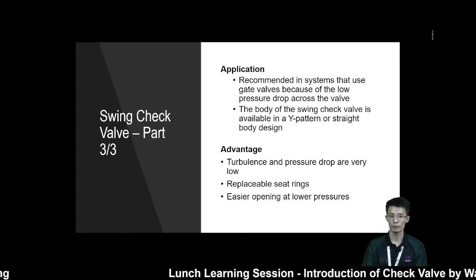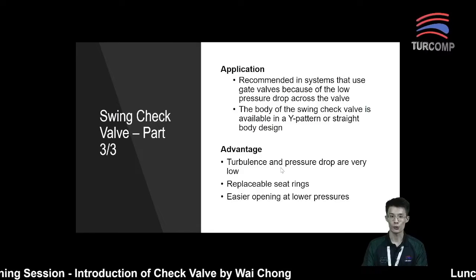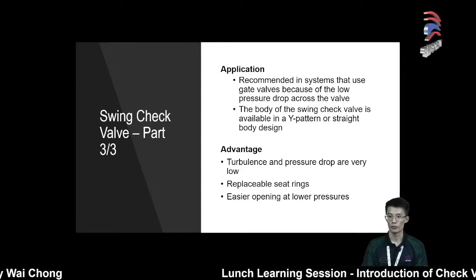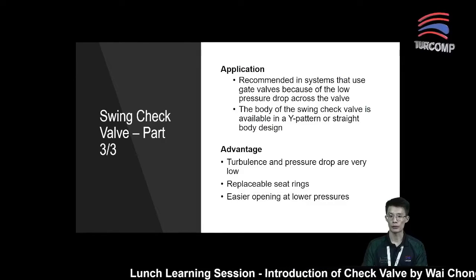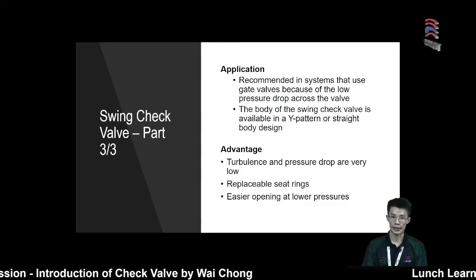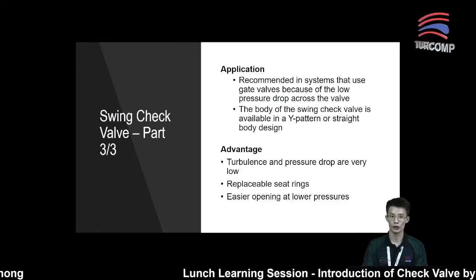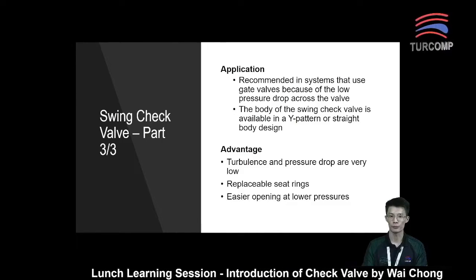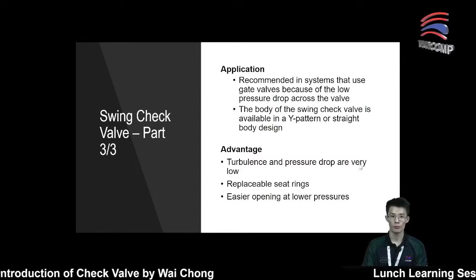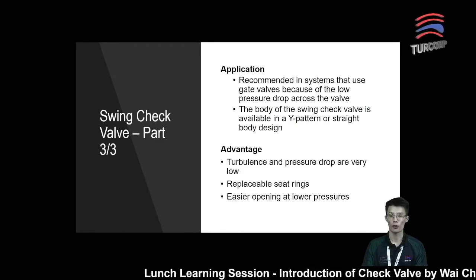For the application, swing check valves are recommended for use in systems that use gate valves, because of the low pressure drop across the valve. The body is available in a Y-pattern or straight body design. For straight body design, they normally have a disk hinge at the top so that it will create a seal against the seat. The swing check valve can also be used in applications with a high percentage of solids and a low on-off cycle.